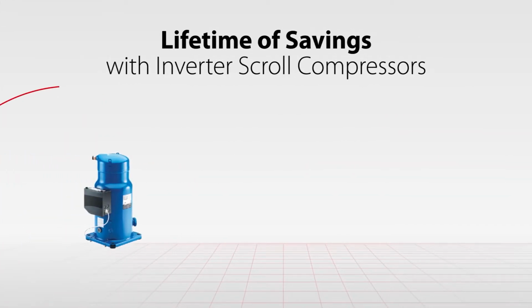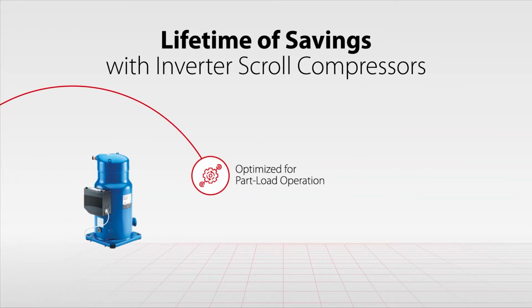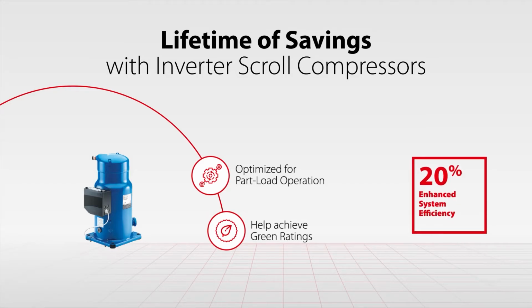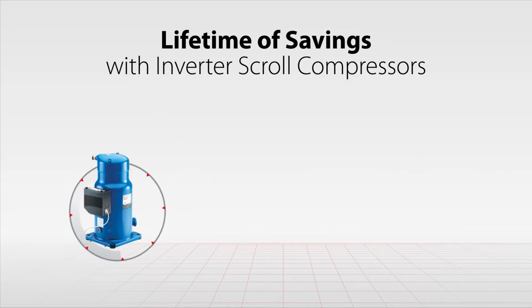Danfoss inverter scroll compressors have been optimized for part load operations to deliver high levels of efficiency for data centers and help achieve green ratings. They also enhance system efficiency by 20%. The inverter scrolls feature extended operating maps to fit CCUs or CRAC units and help lower data center cooling costs.